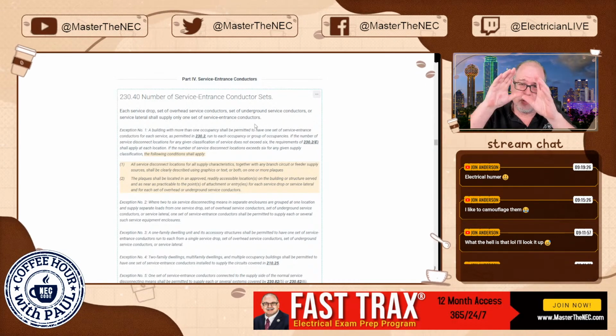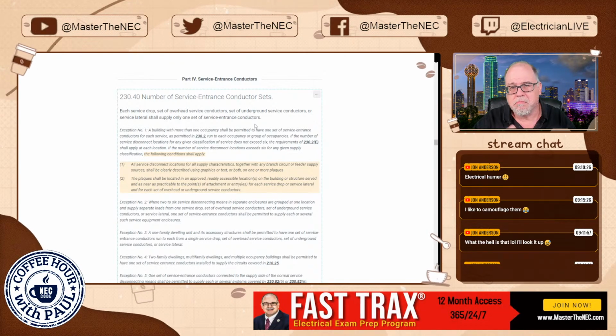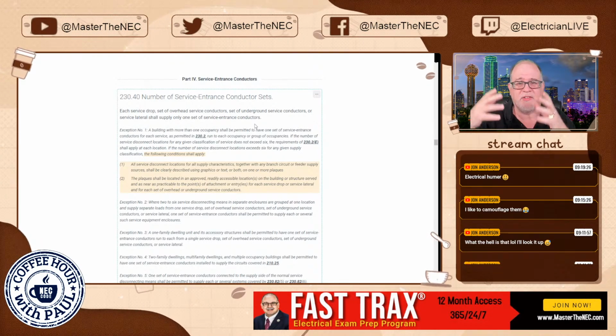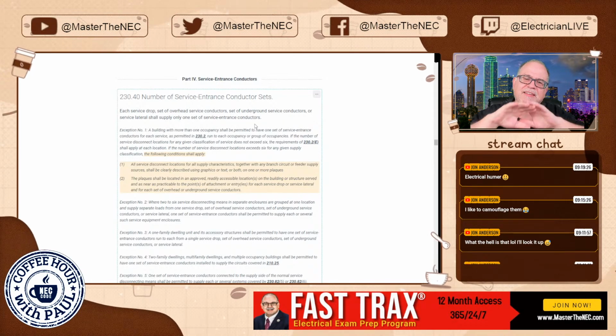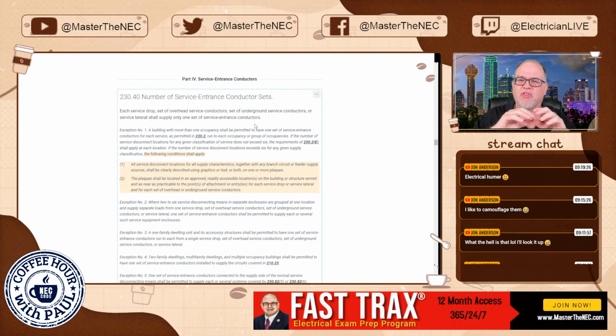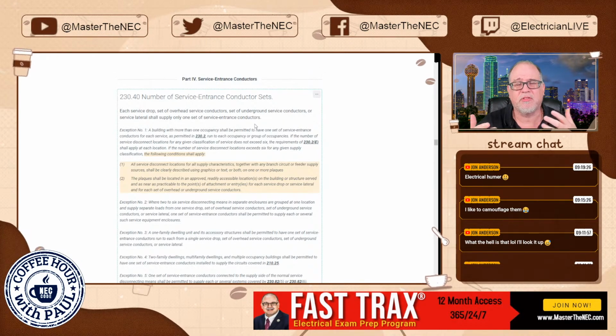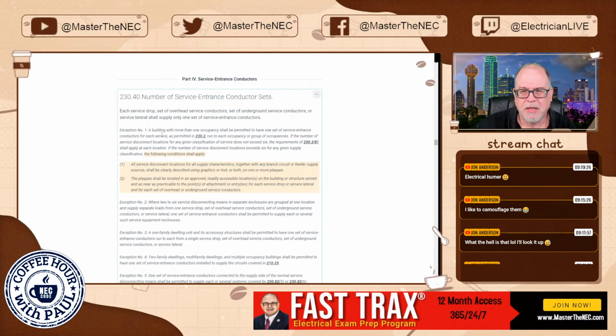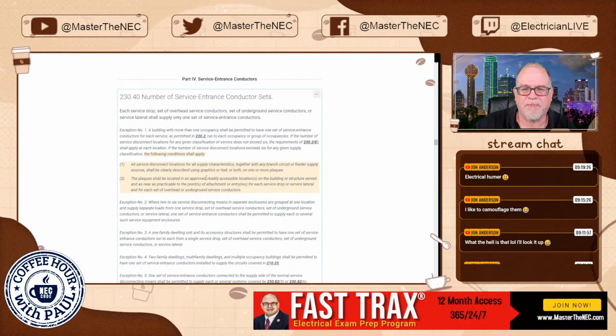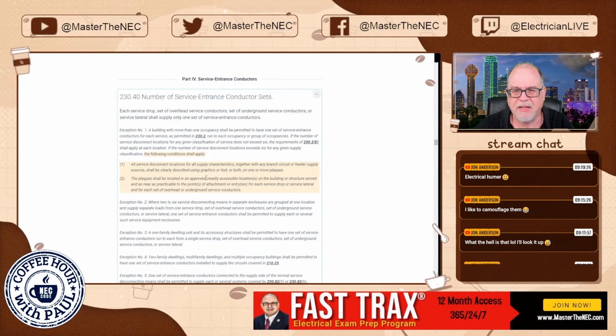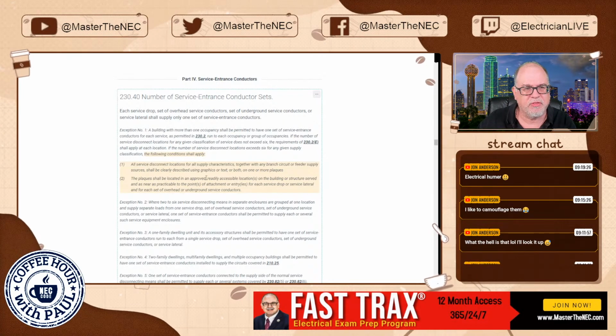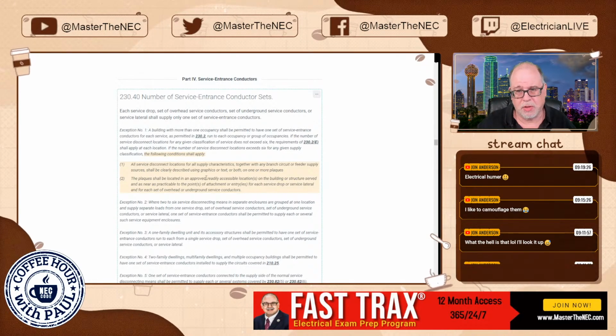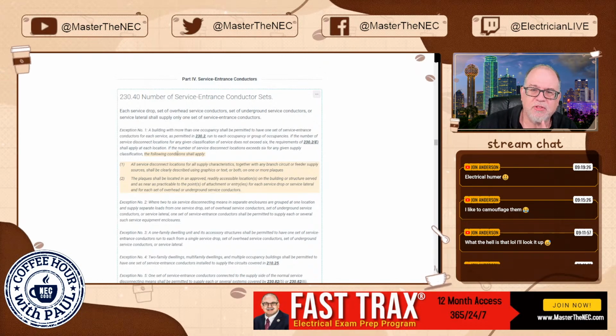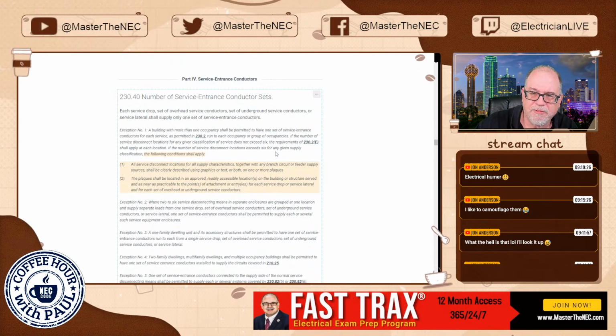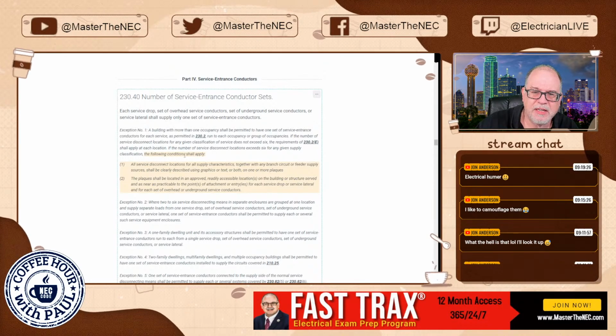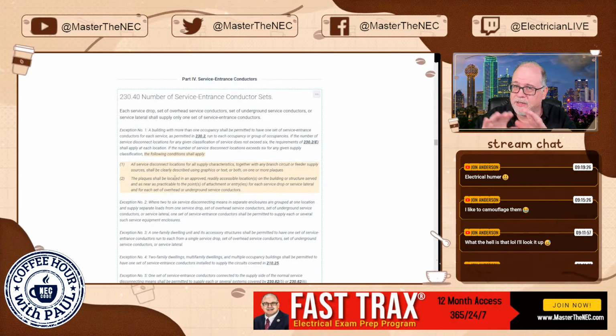So when you drop down to the point of attachment and now you have service entrance conductors, basically it's saying I can have only one service drop, one set of service entrance conductors. But you're thinking, wait a minute. As long as I stay outside of the building, can I wrap that building and run service entrance conductors around the building and then penetrate into these service equipments? Yes, under exception number 1. So there's not a huge change here except for it clarified out the application. And this has to do with the marking requirements, letting you know how many other services are on the building. Okay, so here's what it's added here. Now, if the service disconnecting locations exceed 6 for any given supply classification, the following conditions shall apply. So this is a labeling rule. Don't worry, don't get all upset about it.